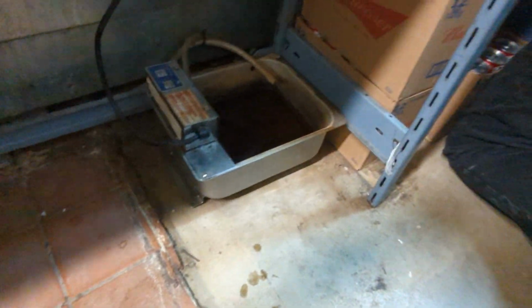They've got two condensate pumps in the back where their storage is. They're on the floor in a spot where, when staff move beer and stuff into that storage area, they just kind of shove the condensate pumps around. So the condensate pipe coming out of the unit got pushed out of the pump, and it was trickling onto the floor instead of into the pump, which is silly. The setup there is that the condensate pump pumps into another drain pan on the floor, a heated drain pan — when the water level hits the float, it turns on the heating element and evaporates slowly.